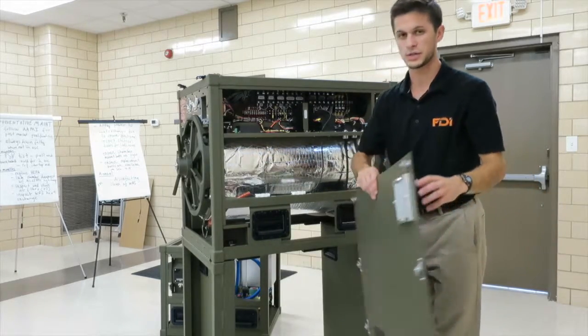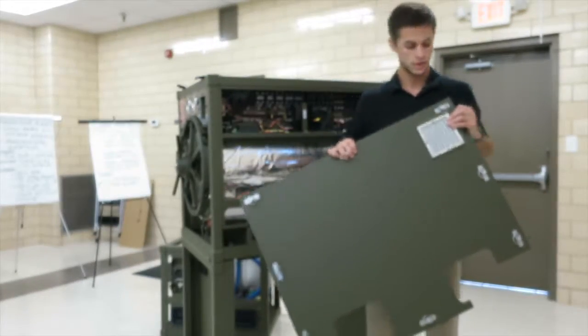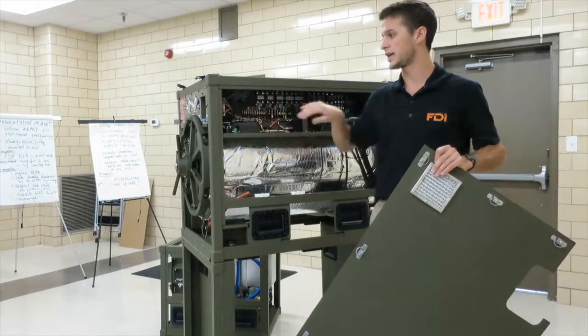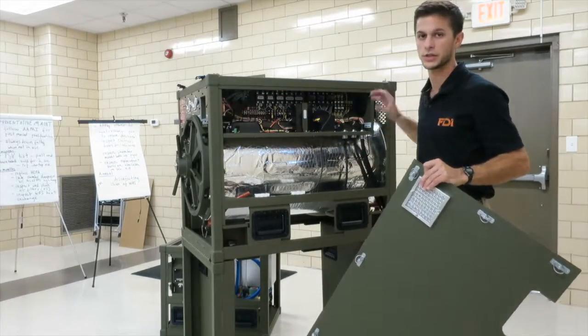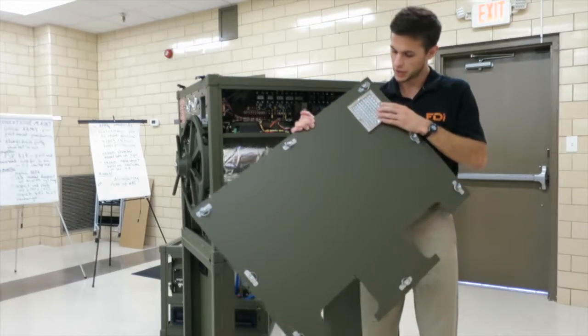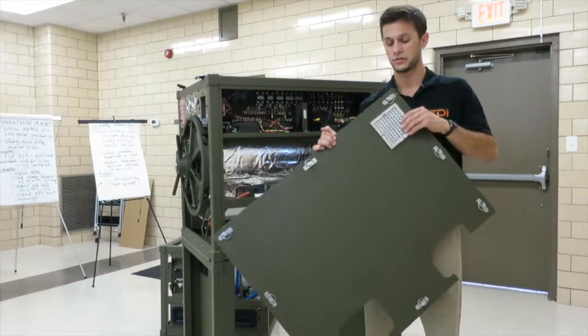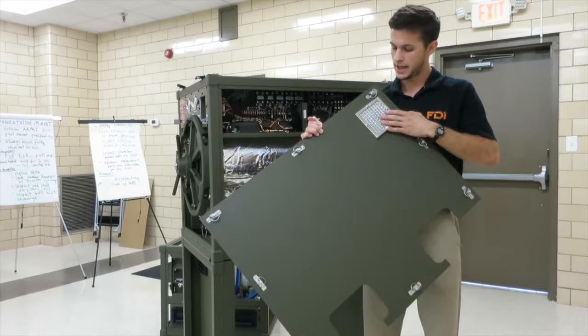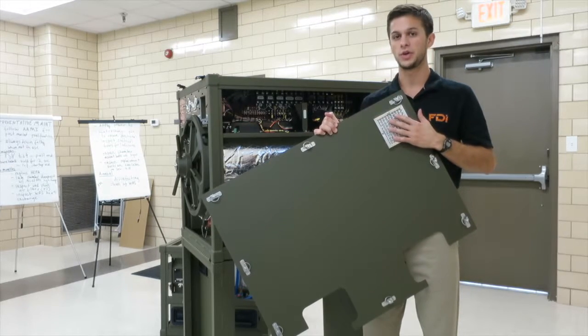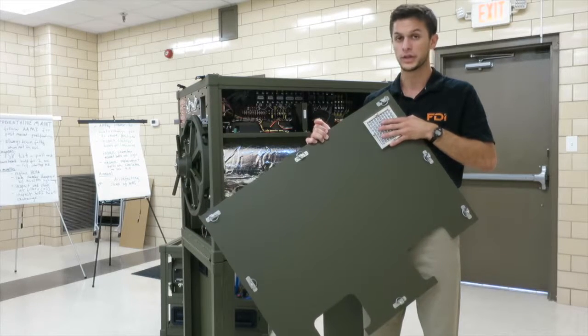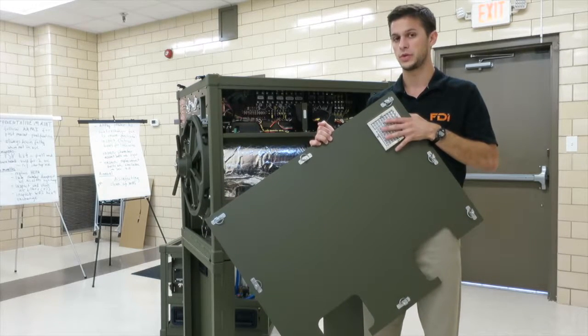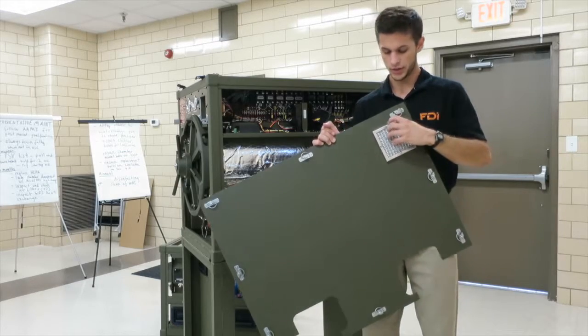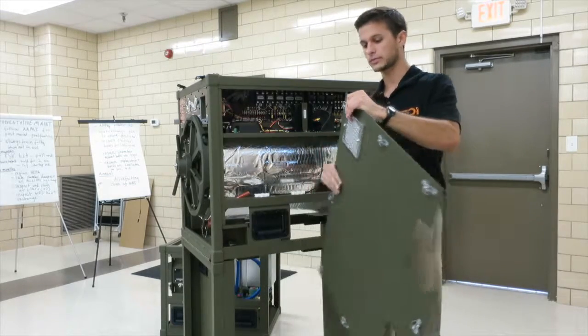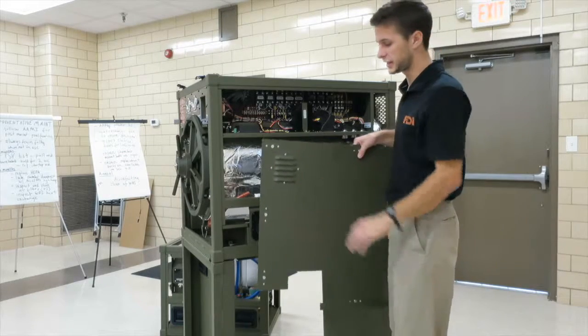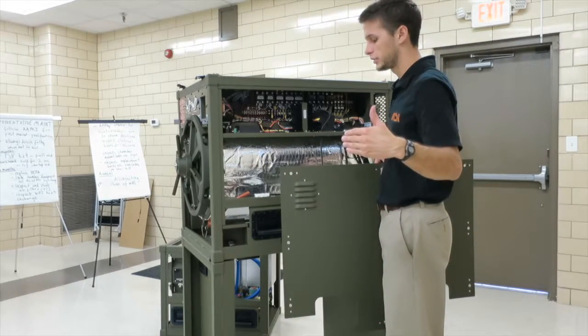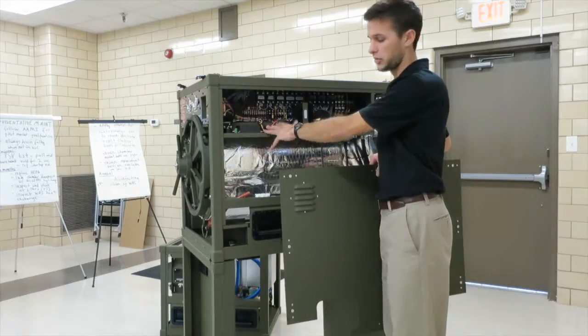The second filter is behind the right side panel, and this filter will sit right here, so the air is going to enter in and draw across the electronics. This filter, again, you can just remove with a Phillips head and some pliers, and you can clean it out with some mild soap and water. If it's getting really gunked up, this is a replacement part, so we can ship you a new one. Be careful when you reinstall it. There is a direction of flow, and if you're facing the panel this way, the arrow should face towards the electrical box.